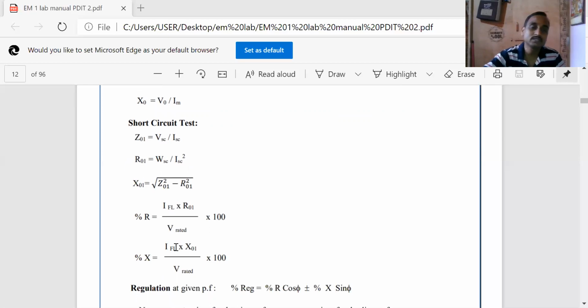Percentage R and percentage X can be calculated using the full load current IFL. The full load current of the transformer is given in the nameplate details. IFL is given by the power rating of the transformer. Suppose you are using a 2 kVA transformer: 2 kVA means 2 multiplied by 1000, divided by the rated voltage of 230 volt. It will be about 8.66 ampere. So 8.66 ampere multiplied by the R01 you calculated, divided by V rated, that is 230 volt, multiplied by 100, gives the percentage R.